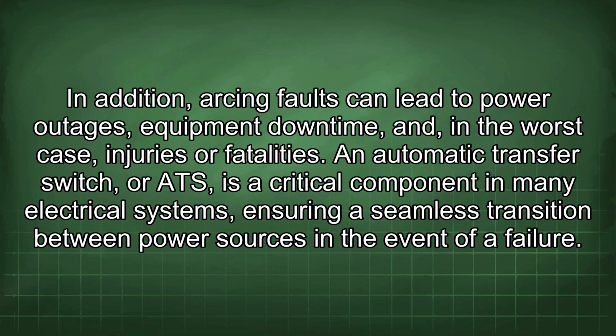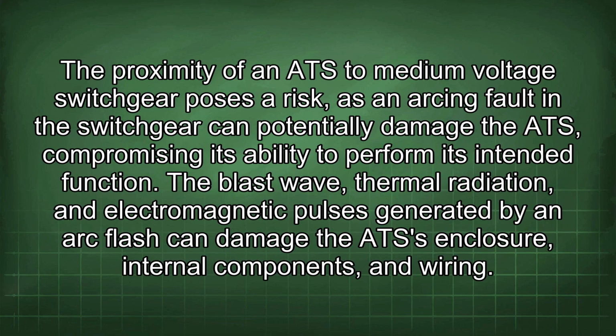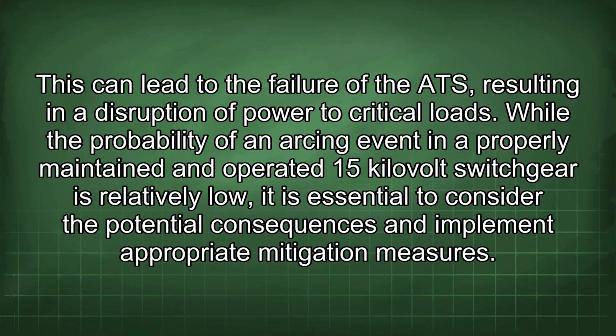An automatic transfer switch, or ATS, is a critical component in many electrical systems, ensuring a seamless transition between power sources in the event of a failure. The proximity of an ATS to medium voltage switchgear poses a risk, as an arcing fault in the switchgear can potentially damage the ATS, compromising its ability to perform its intended function. The blast wave, thermal radiation, and electromagnetic pulses generated by an arc flash can damage the ATS enclosure, internal components, and wiring. This can lead to the failure of the ATS, resulting in a disruption of power to critical loads.